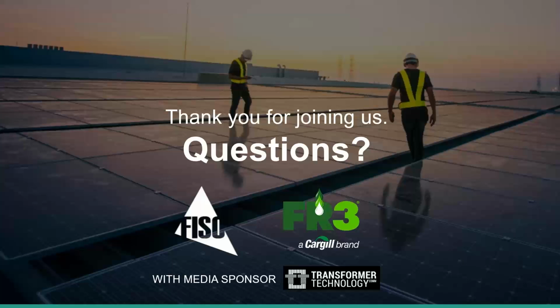Roberto, maybe if you allow me also to join here, I have been involved with a series of tests we did with University of Stuttgart with Professor Tenbohlen and his team in the past. So we compared the dielectric capacity, the breakdown voltage in several different electrode configurations, and we identified that when you get to an extremely sharp edge, a divergent field condition, there would be a difference on the breakdown voltage for the impulse test, and the sharpness level would be a diameter or edge radius lower than 0.5 millimeter, which is typically not acceptable in any transformer.